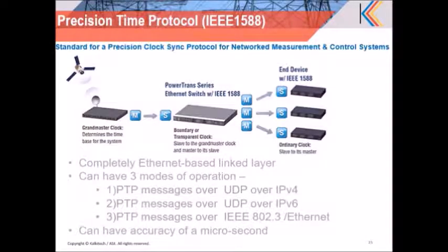Now moving on to synchronization methodology. The edition 1 standard defined the SNTP protocol, that is Simple Network Time Protocol, for synchronization. Here they have introduced another addition, IEEE 1588, which is the Precision Time Protocol used for network-based measurement of timing through the Ethernet layer itself. You can have the devices synchronized. One device will be the master clock, and it can synchronize other devices over the network directly if they support IEEE 1588, so it is completely Ethernet based at the link layer.